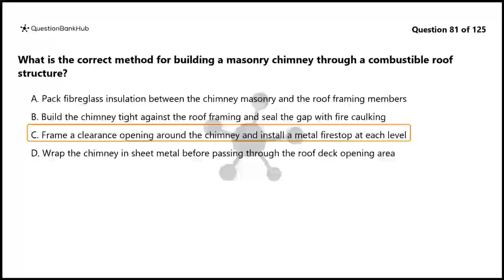The correct answer is C. Frame a clearance opening around the chimney and install a metal fire stop at each level. When a masonry chimney passes through a combustible roof structure, a clearance opening must be framed around the chimney maintaining the required 50 mm minimum clearance to combustibles, and a non-combustible metal fire stop must be installed at each floor and ceiling level to prevent fire spread through the concealed space.